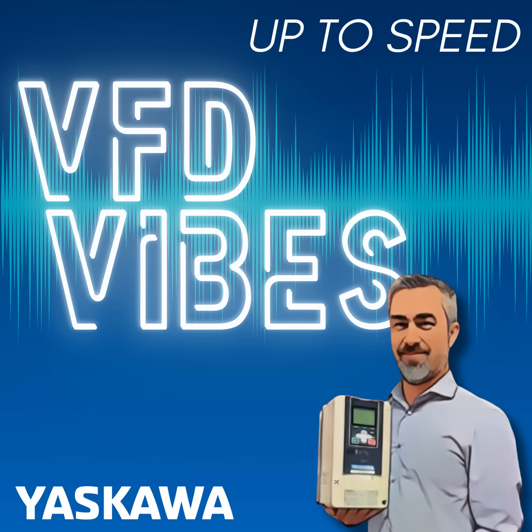So variable speed drives, variable frequency drives, they do have some protection, but not for what we're talking about here today. They protect themselves against many things, including things like momentary overload. So you're running at a certain percent load, and now you go to 150% load for 1 minute, that kind of a thing. They protect themselves against that. That's momentary overload protection. They also protect themselves against temperature because most drives have built-in temperature sensors. And they also protect themselves against excessive regeneration. So when a motor slows down or drive slows down, there's energy that comes back onto the bus, and a drive is going to protect itself against too much of that, which forces up the DC bus voltage. So it protects itself against that also.